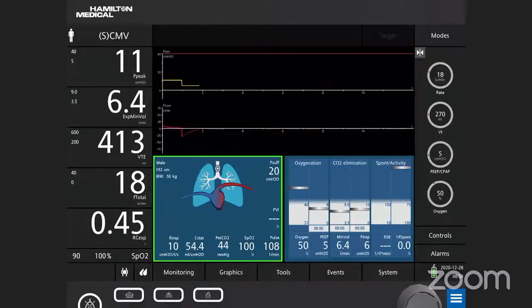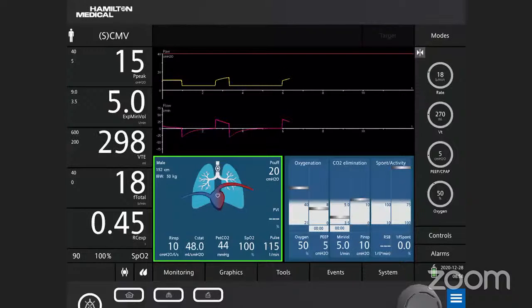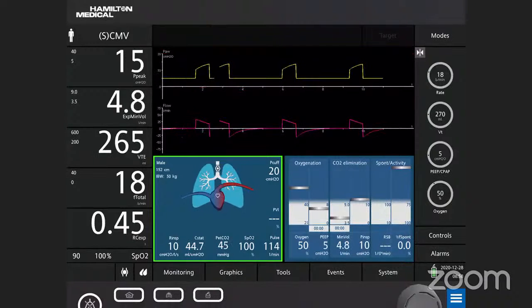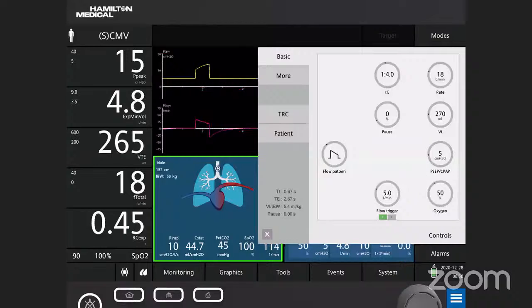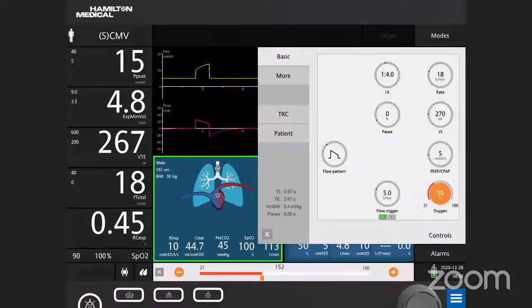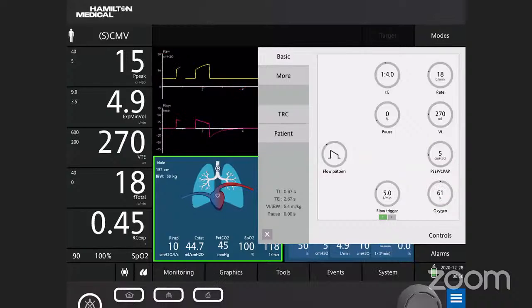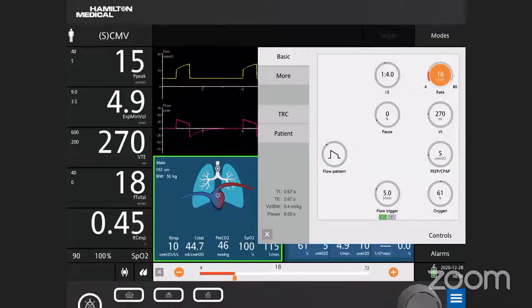So you can see here, the mode is controlled mechanical ventilation, that is your volume control, correct? So what are the controls that you will set? You can see here FiO2 is set. I am just changing it. It is going to 60%. So you have to set the FiO2. Similarly, you have to set the rate. So now I would like to set around 20. You can set whatever you want.